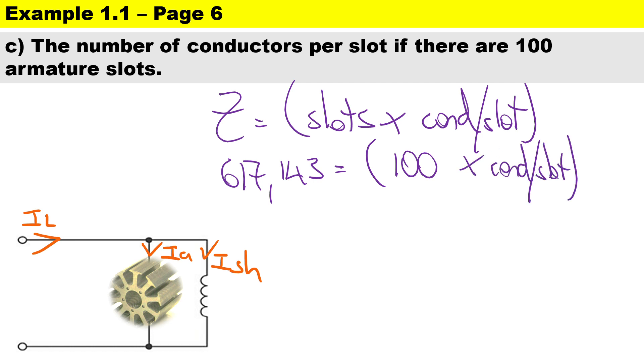And they say there are 100 slots. So now to calculate the number of conductors per slot, just a little bit of mathematics: 617.143 divided by 100, that gives us 6.17. Now you can't have a tiny little piece of conductor, so we round it off. We normally round it up, so it's going to be 7 conductors per slot.